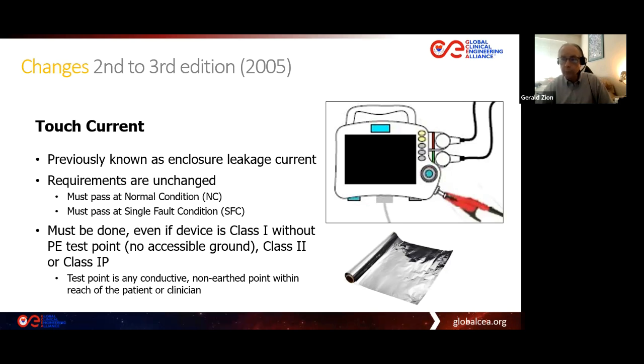Now what we're doing here is we are measuring a capacitively coupled current flow. And that's what's happening for this touch current. Even if the clinician is the pathway for current flow, we have current flowing inside the medical device. We have a plastic enclosure, which is an insulator, and the clinician or the patient are conductors. So we have conductor, insulator, conductor, that's a capacitor. And it will act like a capacitor, and it will produce current flow on the outside conductor, and that we need to measure and minimize.